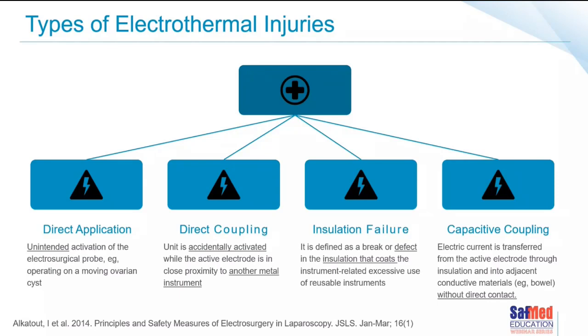Insulation failure, that may be one you know well because it happens not only in laparoscopic instruments but in a lot of other devices as well, where the insulation coat actually becomes defective and something that we need to worry about. Then there's capacitive coupling, and that was a new one for me to learn, although I've experienced this again as a scrub sister, and this is where electrical current is actually transferred from the active electrode through the insulation into adjacent conductive materials like bowel. So that's without direct contact. You can end up burning bowel, you can end up burning ureters, and that's where my experience lies in damaging ureters with lateral thermal damage. The patients became extremely ill, and it's often not caught at the time that it actually happens.